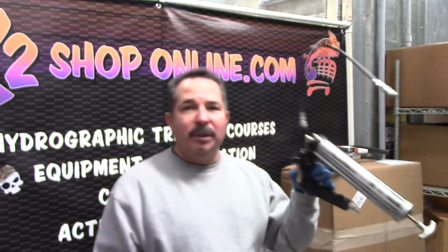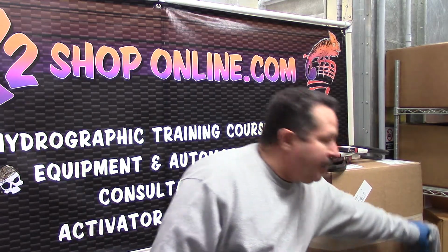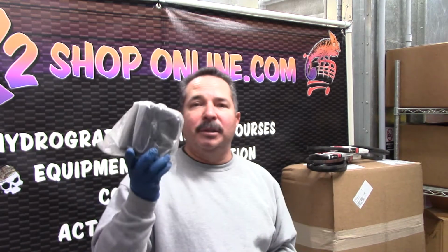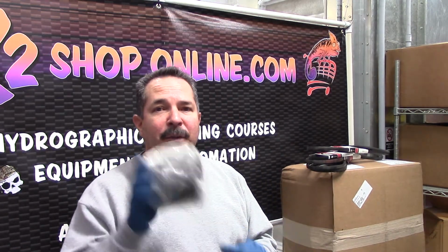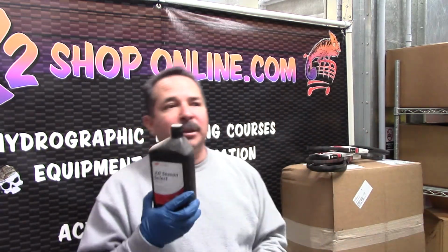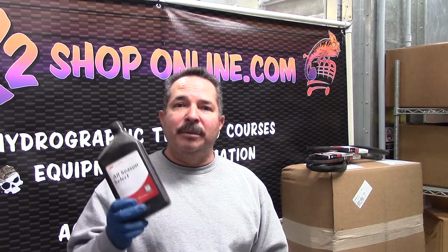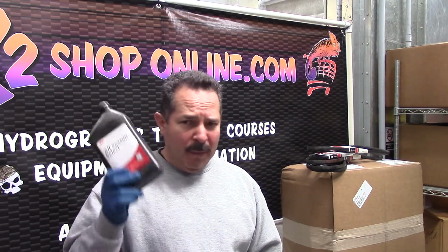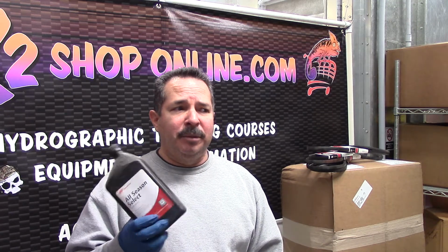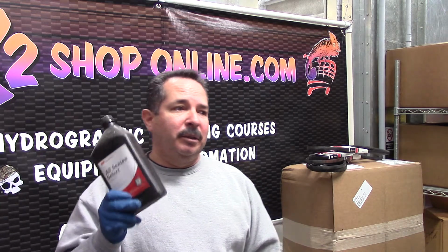You've got motors, then you're going to want to grease them up at least once a year. You've got intake filters on your air compressors. Change out the intake filters at least once a year. And then you've got oil. Now, if your compressor does take oil, chances are it's got an oil level. You guys should take some time to check that. If it's a larger compressor like ours, we've got a 15 horse, you should be changing the oil at least once a year on those things. They're just like cars. The oil does break down. So those are yearly maintenance things.